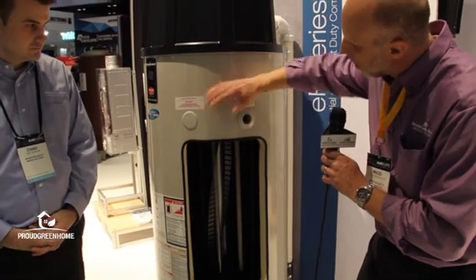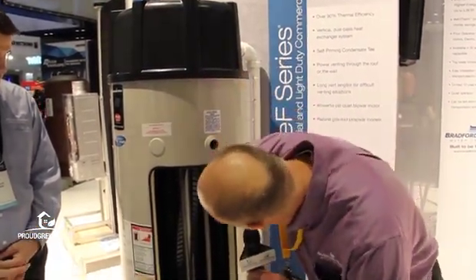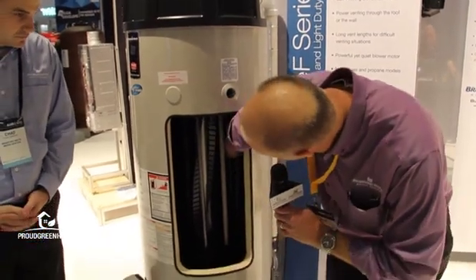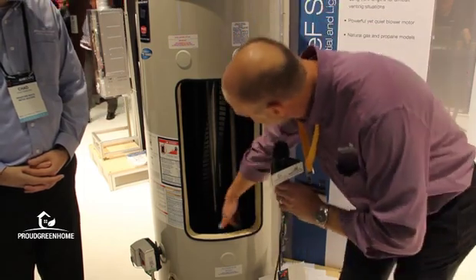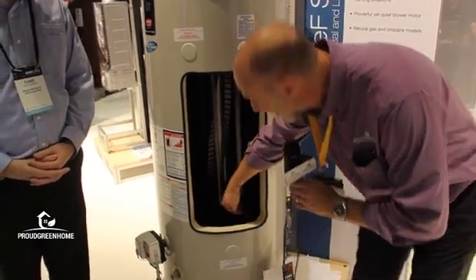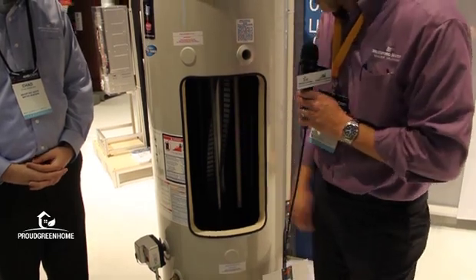There's a collector up here that transfers all that combustion product down what we call a second pass, and there are three different two-inch diameter flue tubes in here. It goes on down, there's a baffle inside, and the combustion product actually leaves the tank at the coldest spot inside that tank.